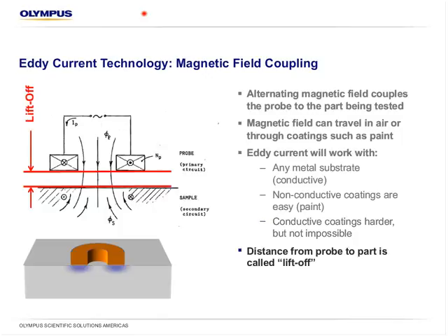Now, the distance from the probe to the part is called the liftoff. You'll hear me speaking about liftoff quite a bit during this presentation - it's one of the key variables in this solution. The distance from the probe to the part would typically need to remain minimal, and what prevents the probe from being as close as possible to the part under test is only the paint thickness. So the paint thickness is pretty much the equivalent of the liftoff in this application. Liftoffs of up to 2 millimeters are possible, and a little bit more.